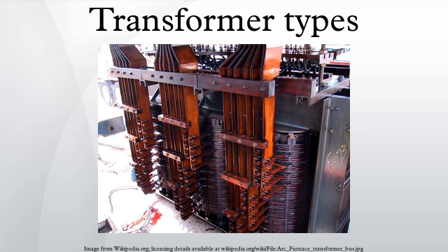If a winding is connected to earth, the earth connection point is usually the center point of a Y winding. If the secondary is a delta winding, the ground may be connected to a center tap on one winding, or one phase may be grounded. A special-purpose polyphase transformer is the Zigzag Transformer. There are many possible configurations that may involve more or fewer than 6 windings and various tap connections.